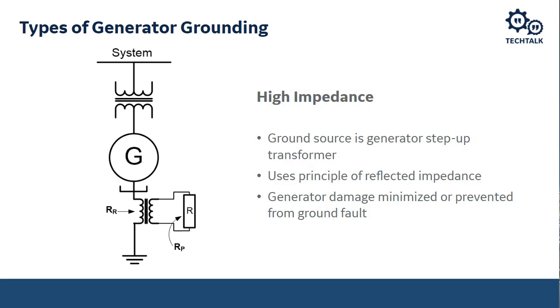It's typically used when the generator is connected to a GSU, or a step-up transformer. So the ground source is a generator step-up transformer. And it uses the principle of reflected impedance, as I mentioned, within the grounding transformer. And the important thing is the generator damage is minimized or actually prevented from a ground fault. So we can easily detect the ground fault. We'll talk next, in the following slides, about how we protect for this high impedance fault. Because as I mentioned, when you have a high impedance grounded system, the ground fault current is going to be almost undetectable to certain overcurrent protection elements. So we need to use alternate protection elements to be able to protect a high impedance grounded generator.